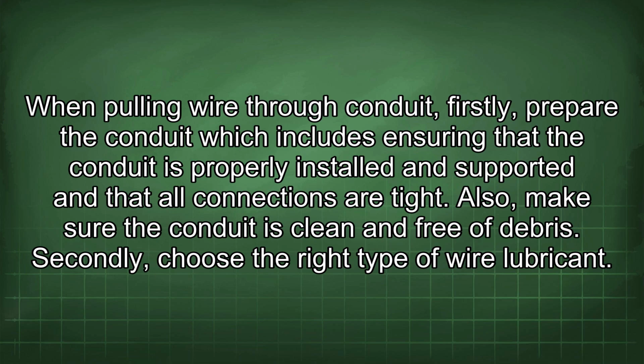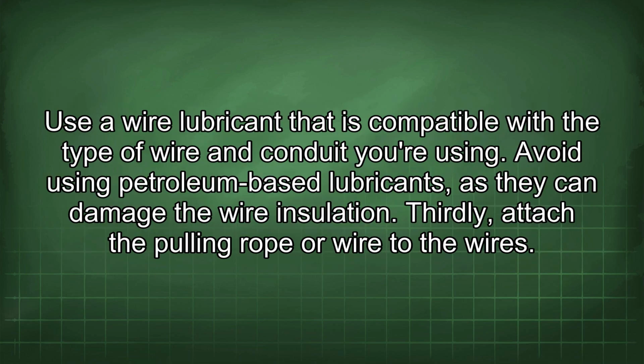Also, make sure the conduit is clean and free of debris. Secondly, choose the right type of wire lubricant. Use a wire lubricant that is compatible with the type of wire and conduit you're using. Avoid using petroleum-based lubricants, as they can damage the wire insulation.